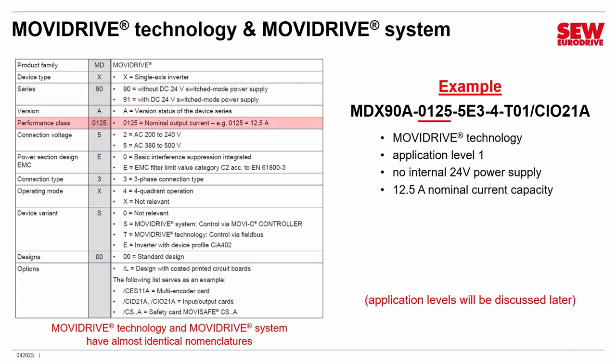The 0125 is a very important number — it tells you how many amperes the device can supply, in other words its capability and what kind of motor you could connect to it. SEW always places an imaginary decimal point between the last two digits, so 0125 actually means 12.5 amperes. Next, a number indicates the operating voltage: in this case a 5 means it operates on 380 to 500 volts, so probably 460 to 480 — very common in industrial settings.